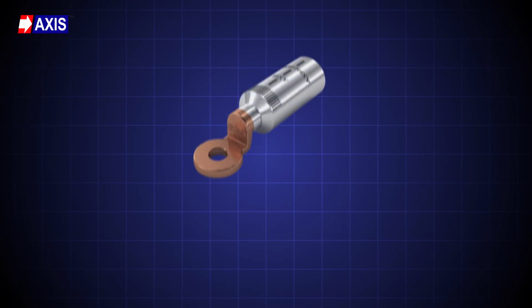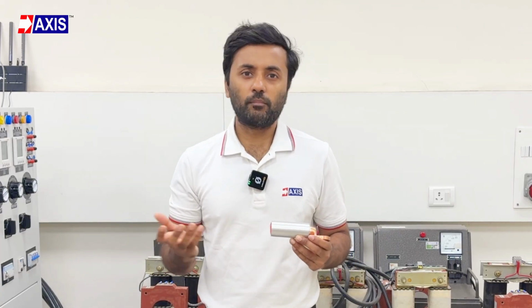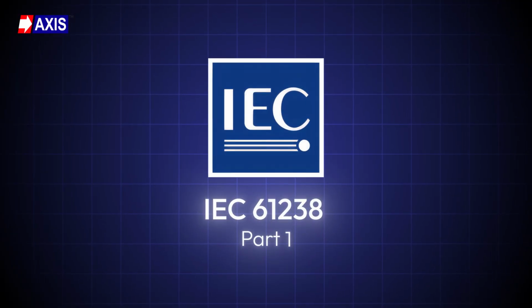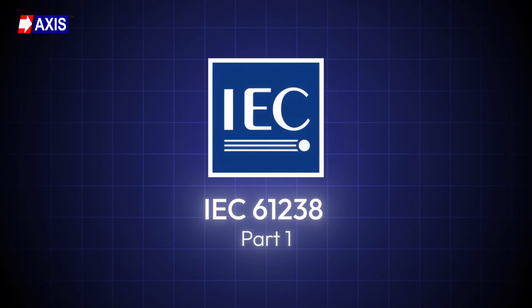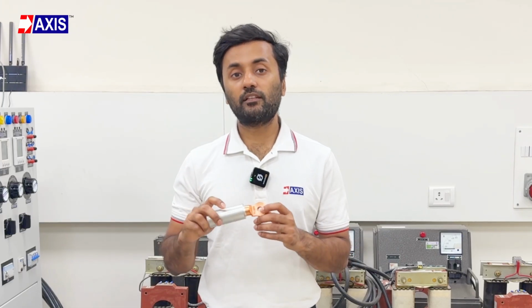Now let's start with bimetallic lugs. A lug is simply a component used to connect an electrical cable to equipment or a bus bar. In solar plants, bimetallic lugs are installed inside the combiner box to ensure electrical safety. These lugs should comply with IEC 61238 Part 1. This standard specifies the requirements for electrical connectors and lugs.